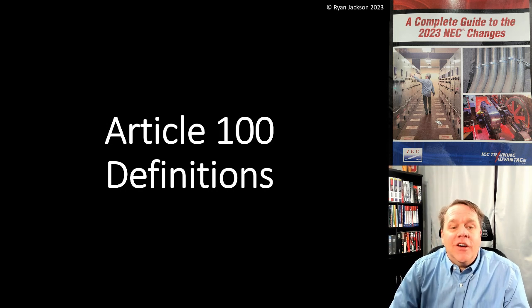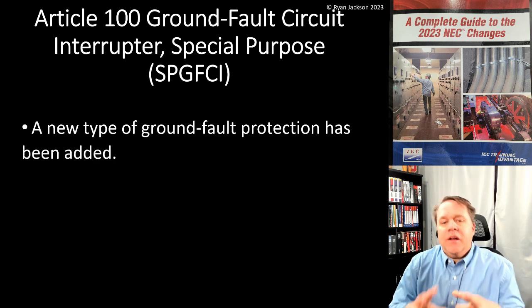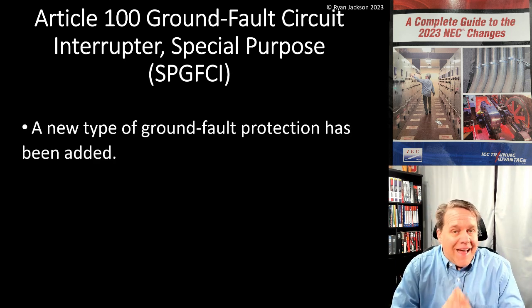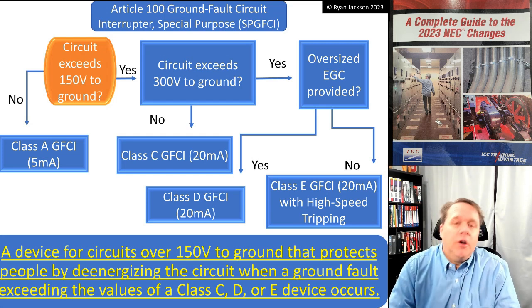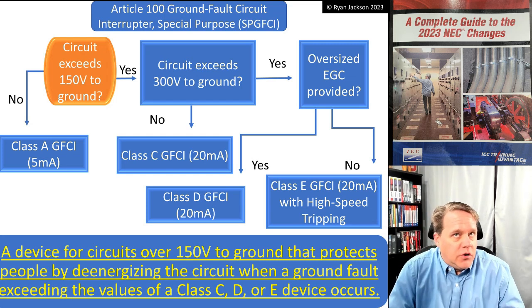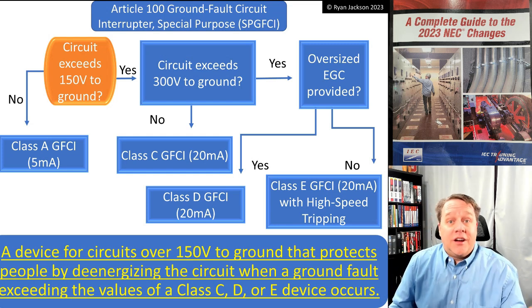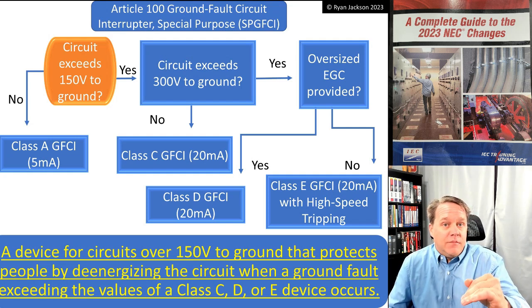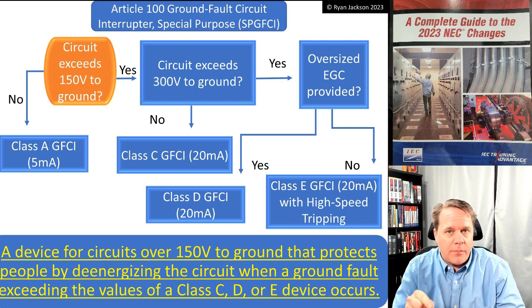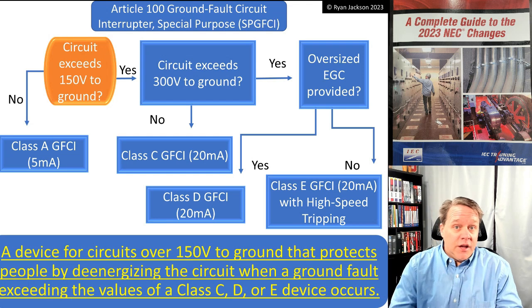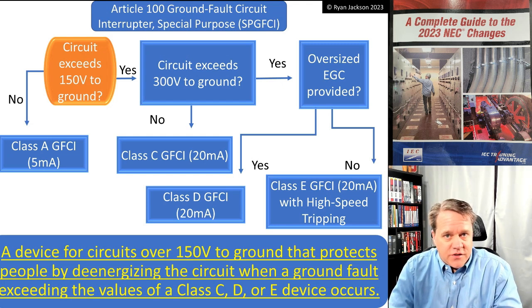The next definition we're going to talk about is Article 100 — ground fault circuit interrupter, special purpose, or SP-GFCI. This is a new type of ground fault protection added to the 2023 NEC. If you go back to Article 100 and read the definition of a GFCI, you'll find it's a device that opens when ground fault current exceeds six milliamps but does not open when it's less than four milliamps — that's a Class A device, which is what we've been using historically.